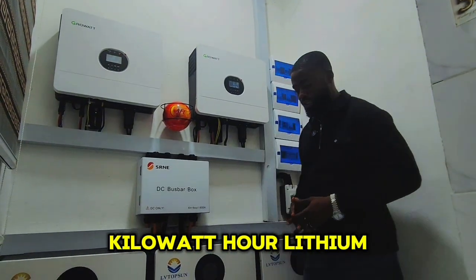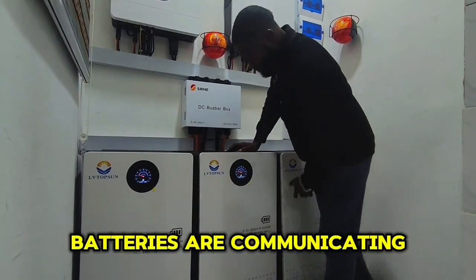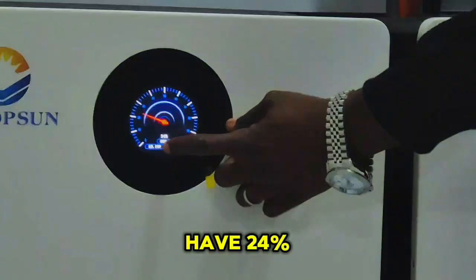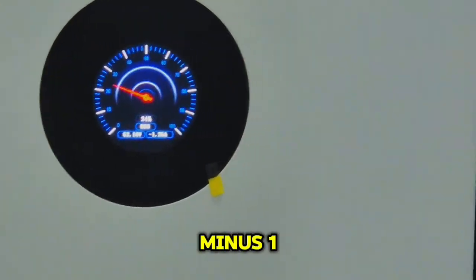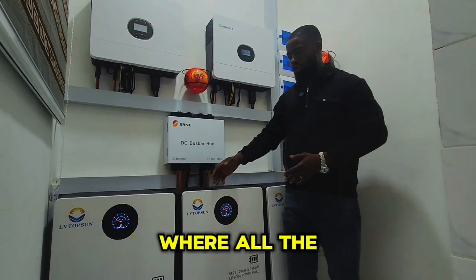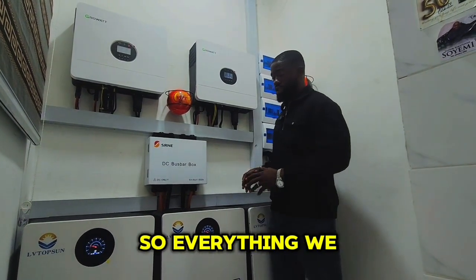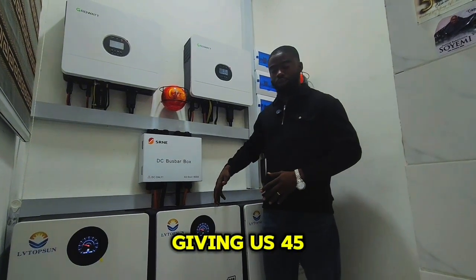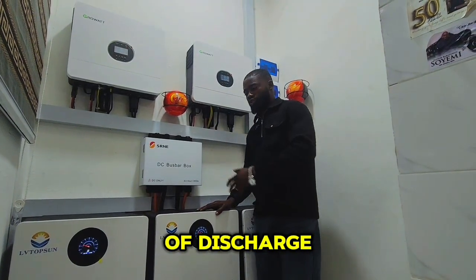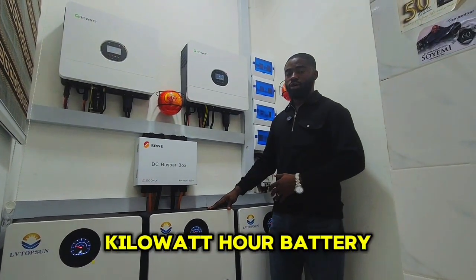Down here we have three units of 15 kilowatt-hour lithium batteries from LVTOPSUN. Each battery is connected in parallel so all three are communicating together working as one. On the screen of each battery you can see 24% charge and the system is showing discharge. All batteries are connected to a bus bar in parallel — not in series, as these units don't accept series connection — giving us 45 kilowatt-hours total. The battery comes with a five-year warranty, 6,000 life cycles, and 80% depth of discharge.